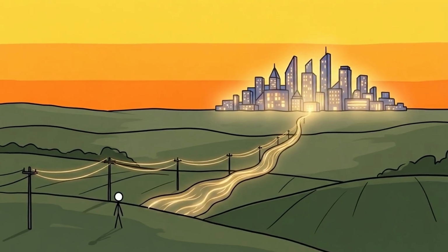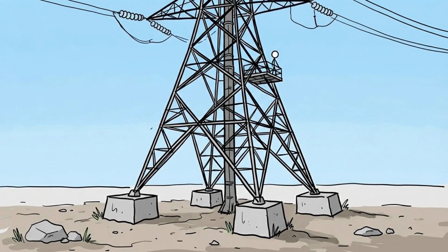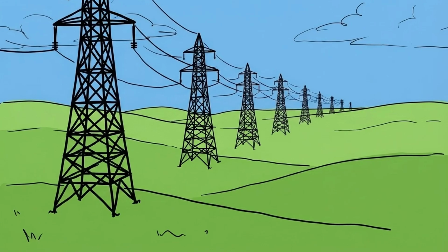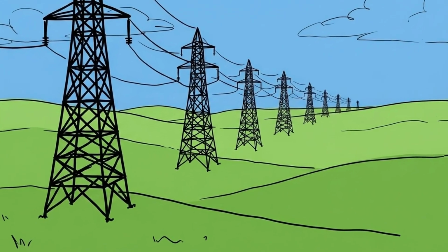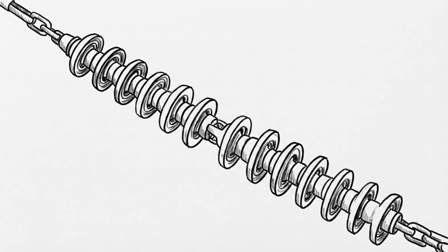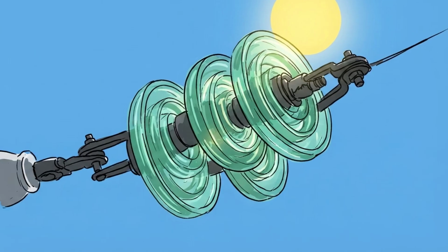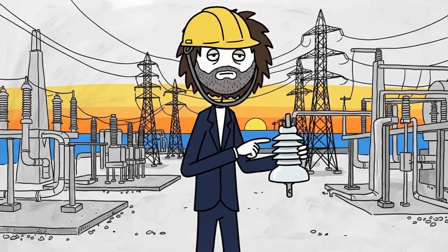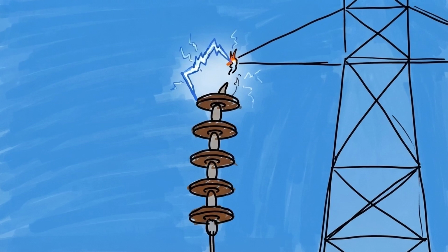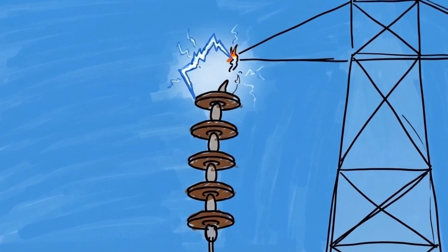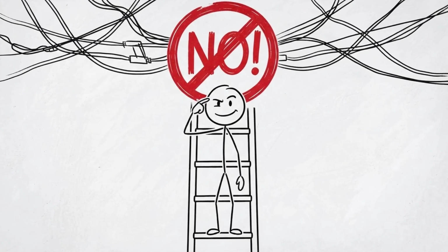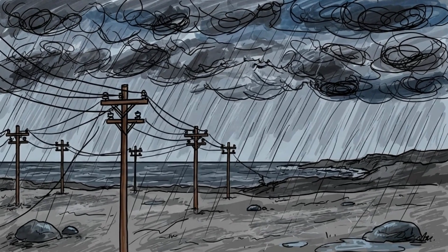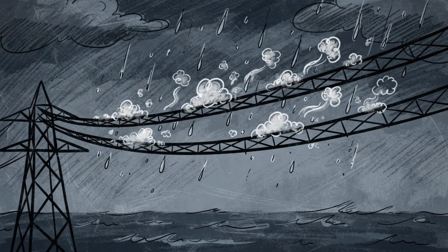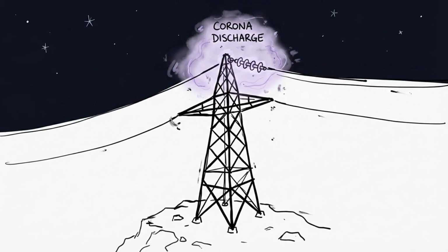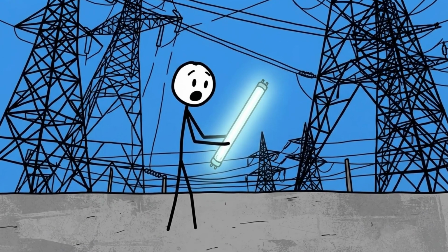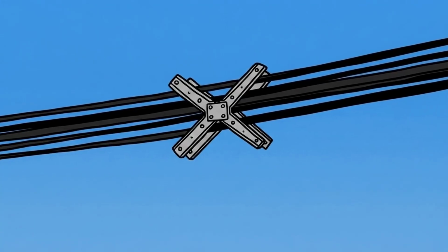Once the electricity is boosted to these extreme pressures, it flows out onto the iconic high-tension sky highways: massive steel lattice transmission towers marching across mountains, rivers, and highways. If you look closely at these giant towers, you will notice that the aluminum conductors never actually touch the steel frame of the tower. Instead, they hang suspended from long strings of grooved porcelain, glass, or polymer insulator bells. Because hundreds of thousands of volts of electricity will happily jump through several feet of open air to find a path to the ground, these insulator strings create a long, winding physical barrier that prevents lethal arc flashes from jumping into the grounded steel tower.